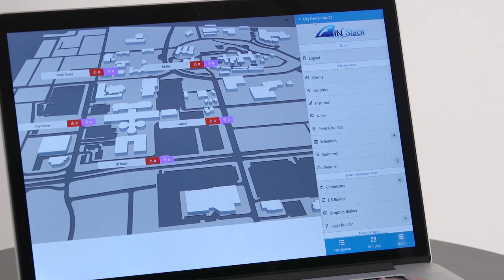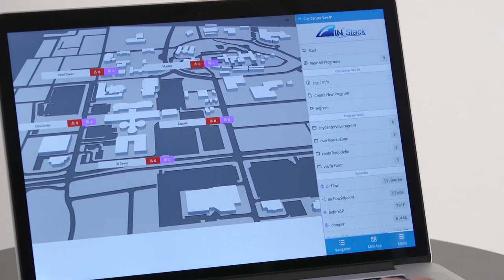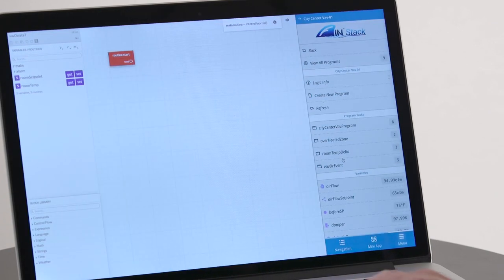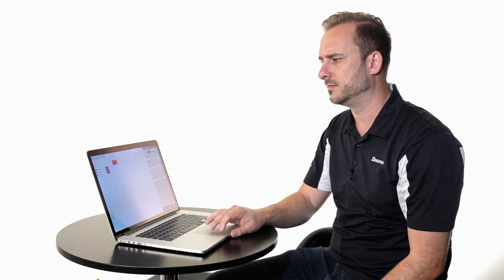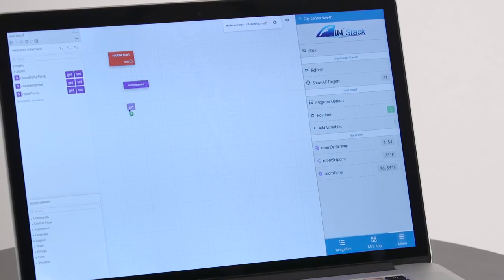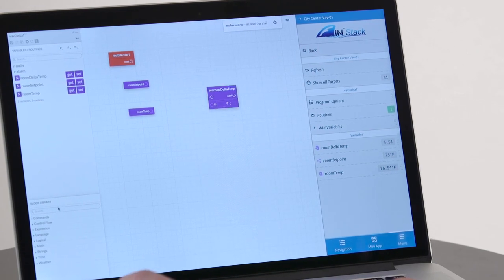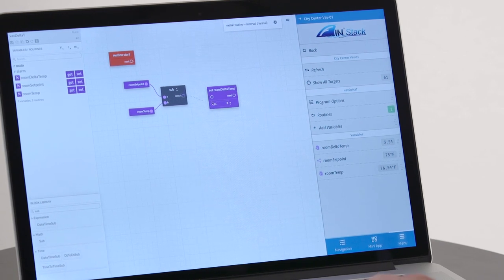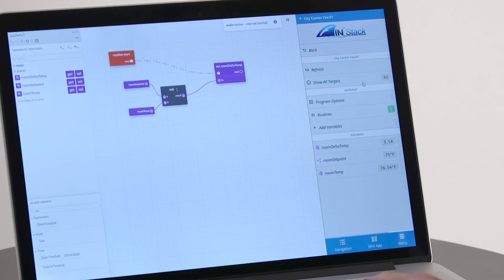Just like making air handlers and floor plans, our control logic is all workflow based as well. Navigate to City Center VAV One and go into the logic builder. Create a new program — let's create a VAV delta T program for every VAV in my database and select the room temperature, set point, and delta T. What you're seeing is the wire sheet running in the browser — no Java plugin, 100% in the browser. I'm going to drag my set point and my room temperature to get the delta T, then search for and find a subtract block. This program, when I hit the save button, now runs on every single VAV in your entire enterprise — whether it's one, 61, or a thousand. No more copying, no more linking. You write one program and it runs everywhere using haystack tags.